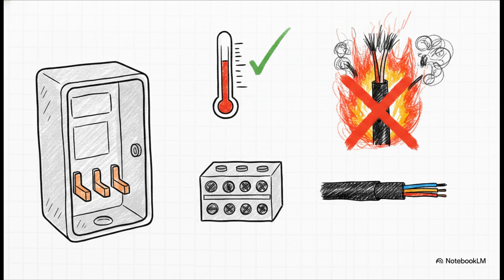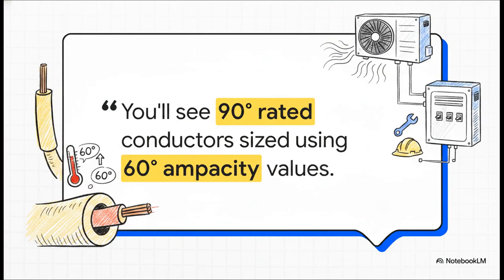Because of these physical connection points, the safest, most code-compliant move is to size your conductors using the 60-degree ampacity column from the NEC table. It lines up perfectly with real-world inspection practices and completely keeps us away from dangerous, overheating assumptions. This quote from our source material really hits the nail on the head. You'll frequently see 90-degree rated conductors sized using 60-degree ampacity values in real-world installations.